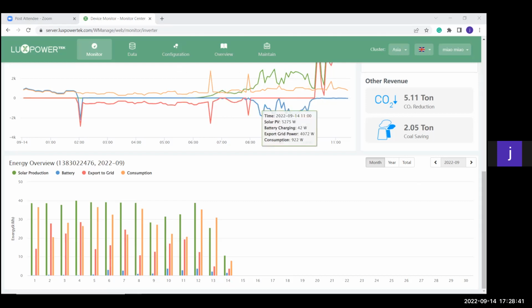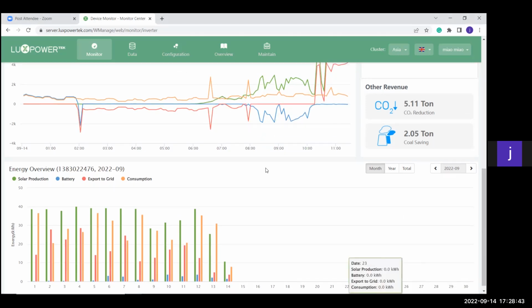Yes, the grid will always be opposite to what's on the graph, as you can see here. He only uses his batteries as backup. He doesn't want to use his batteries at night. He wants them for backup only, this line. So you can see the grid mimics that one here. If your red line is there, and like here, there was no grid, you can see your battery and your PV were working together to provide to the loads at that specific instance.